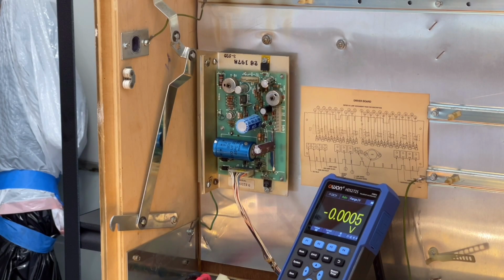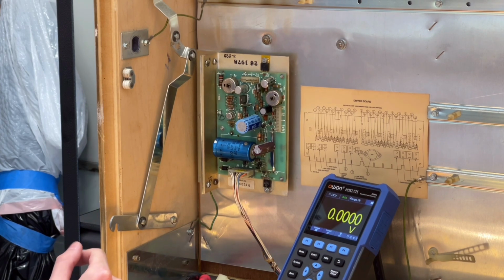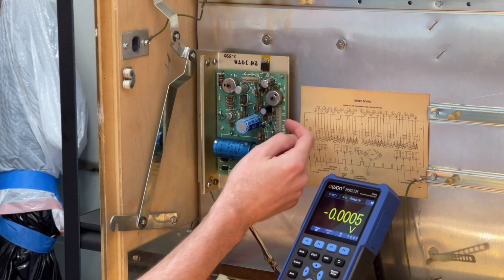I did some more reading on this machine, and it turns out that the 60 volts and 42 volts use a different ground than all of the other voltages. So that would explain why we were seeing nothing when probing those two pins. The ground used for the 60 and 42 volts is actually the one on the connector itself.